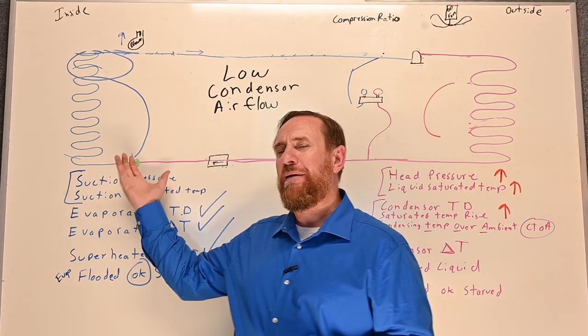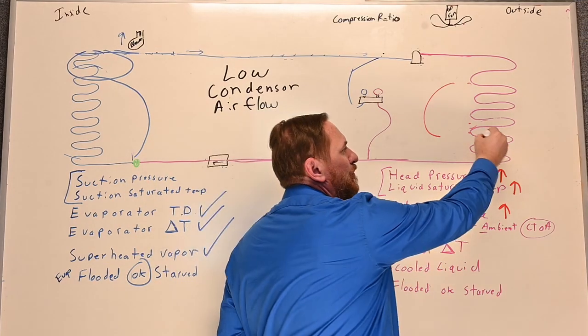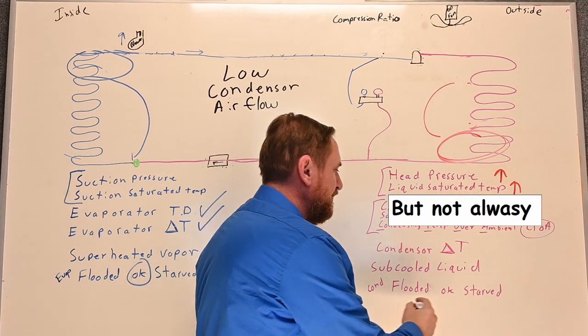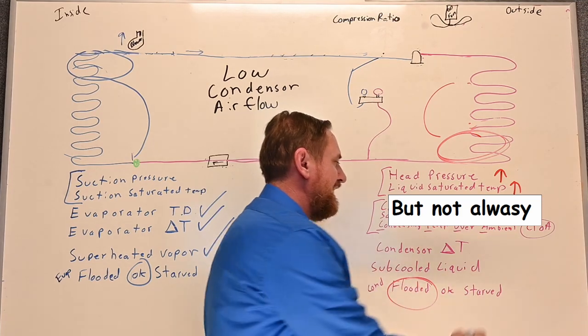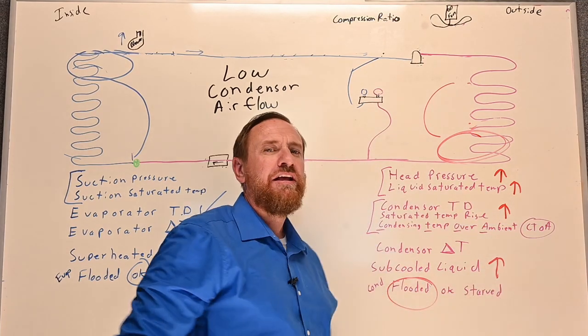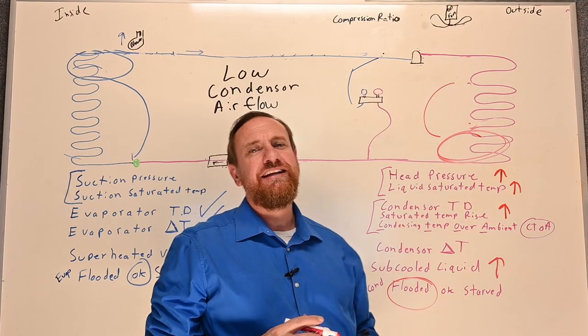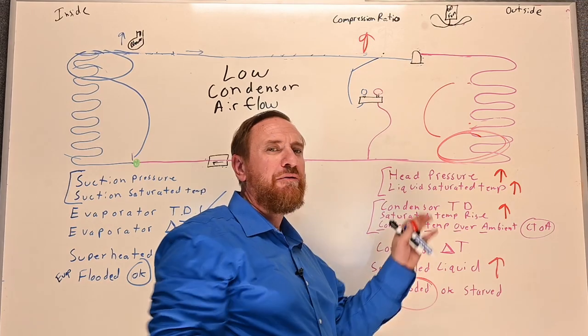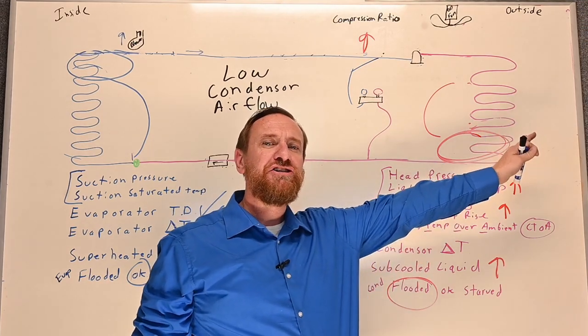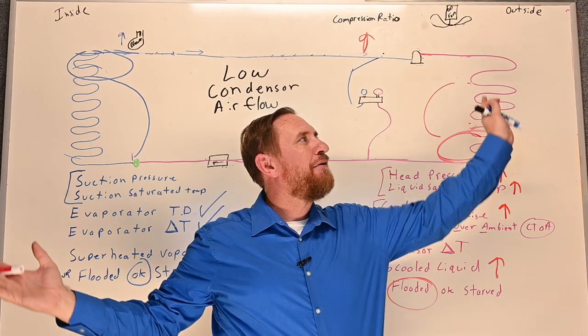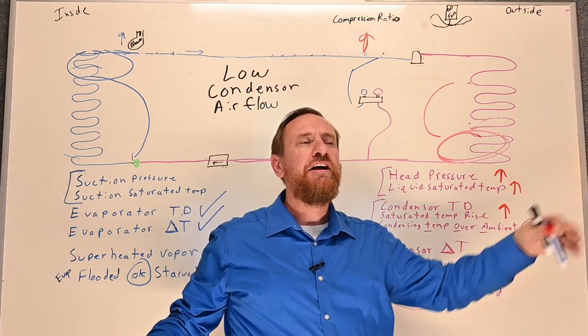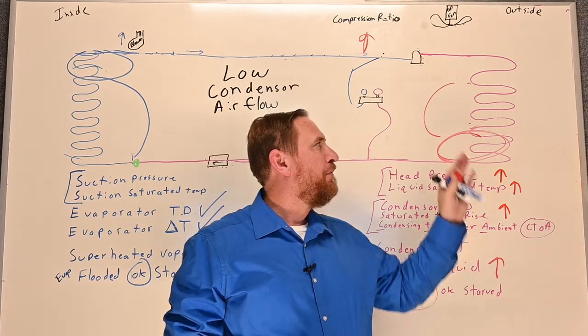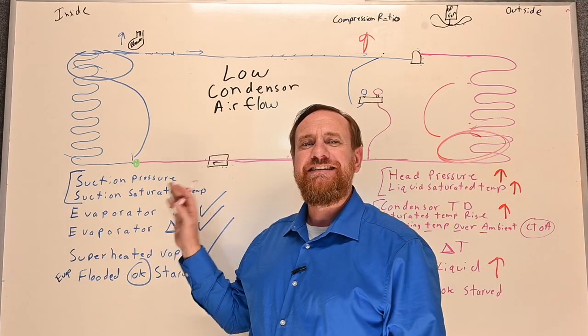However, because all that pressure is backing up on the high side, we'll end up stacking more and more liquid refrigerant on our condensing coil. So a lot of times you'll see a flooded condenser because of that higher amount of sub-cooled liquid — all that extra work is going against the compressor. On top of this, you're going to see a much higher compression ratio because we're having to build higher and higher pressure on the outside while the inside stays the same. These are some of the effects you'd see with blocked airflow and a TXV.